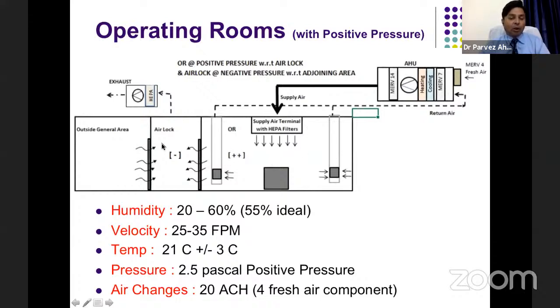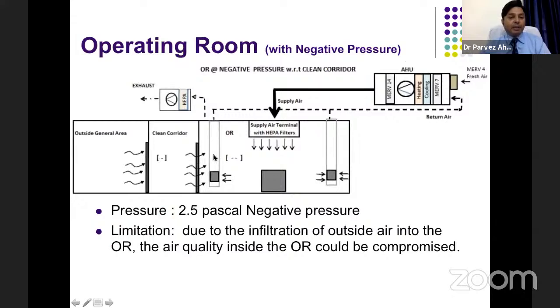Then there is an airlock, an area which has a negative pressure, and the outside general area is again positive pressure. So from the operation theater, air moves towards the negative pressure area, and from there one exhaust goes out through the HEPA filter. That HEPA filter cleans the contaminated air before discarding it into the environment.